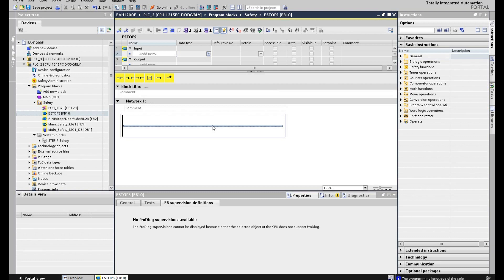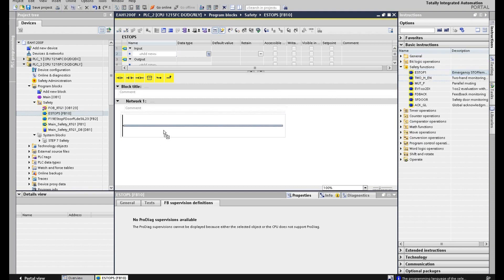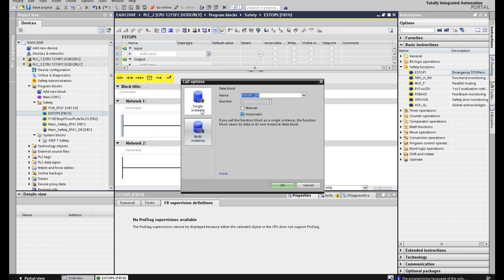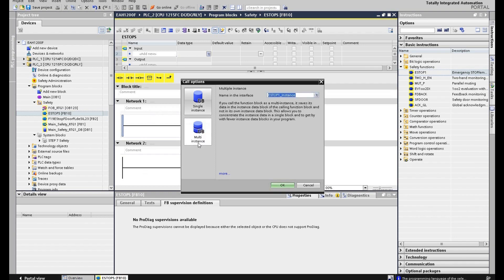In this e-stops function block, we will program all the function blocks for e-stops. For example, if your system has multiple e-stop buttons, we will program all of them here. For the first e-stop, we will drag the e-stop block here. If we select multiple instance DB, this FB10 instance DB will serve for all the e-stops inside this function block 10, keeping things clean. If we set individual DB, there will be many instance DBs in the background, which gets messy. So most of the time we select multiple instance.